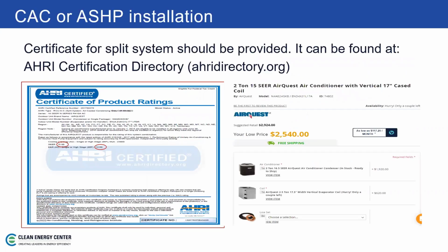So here's what we'd be looking for. There was a question come up, so I just went online. AirQuest is a carrier product. It's like a lower end piece of equipment, but they do have a piece of equipment match, an indoor coil and an outdoor unit.